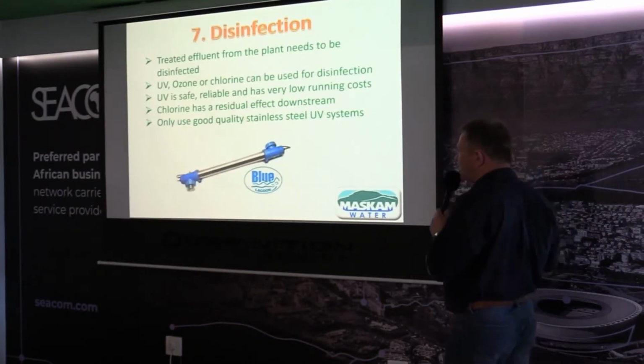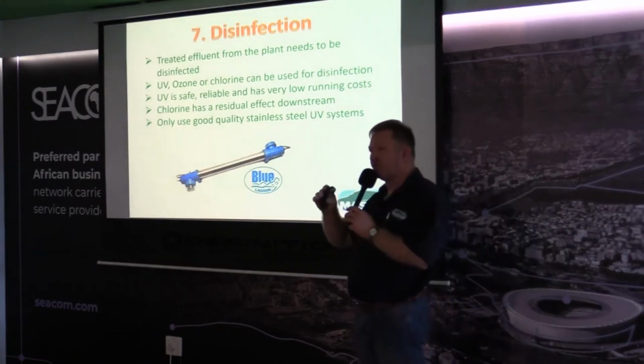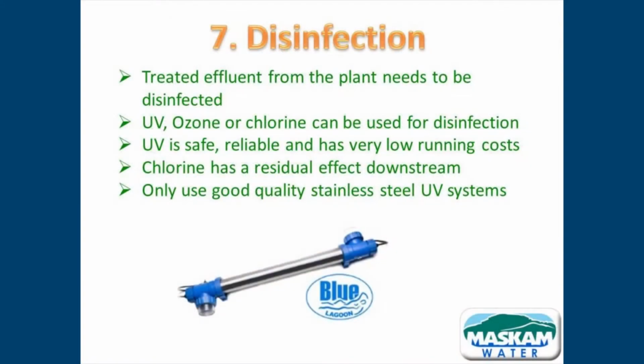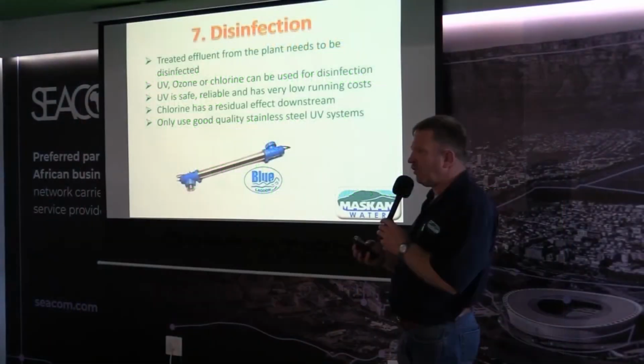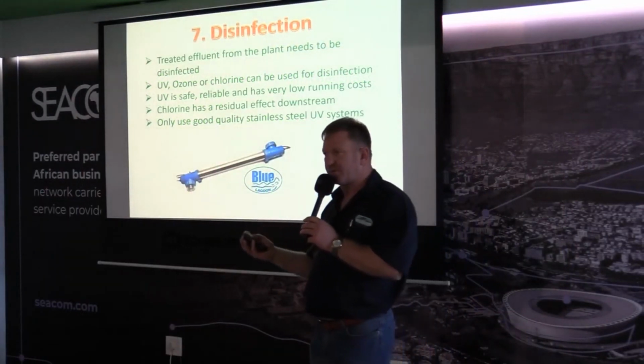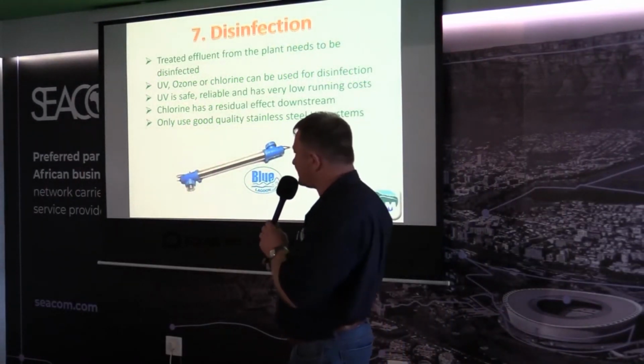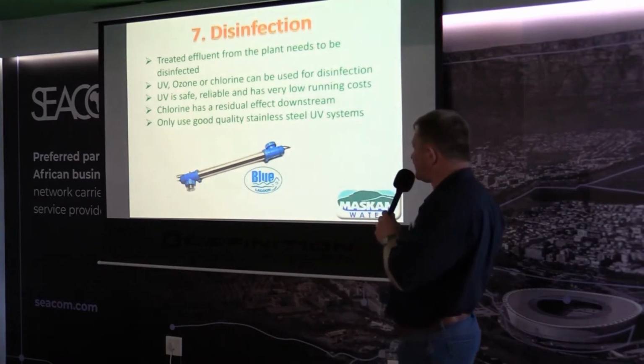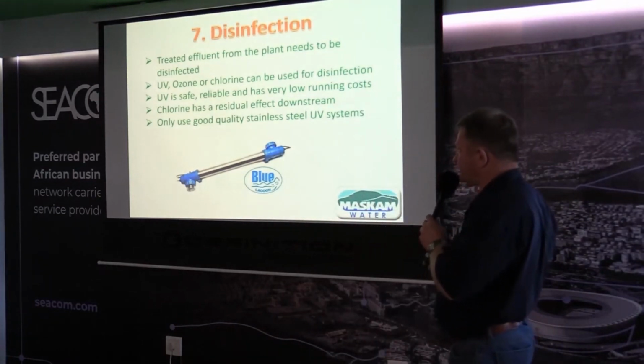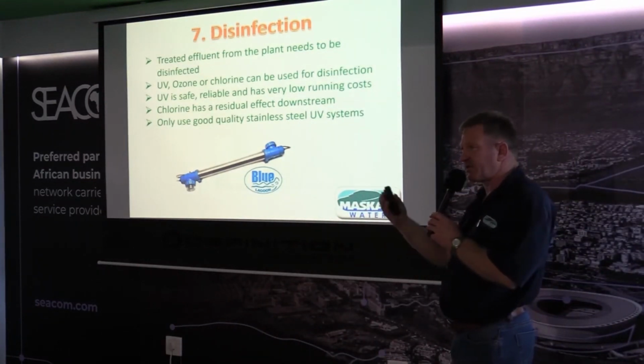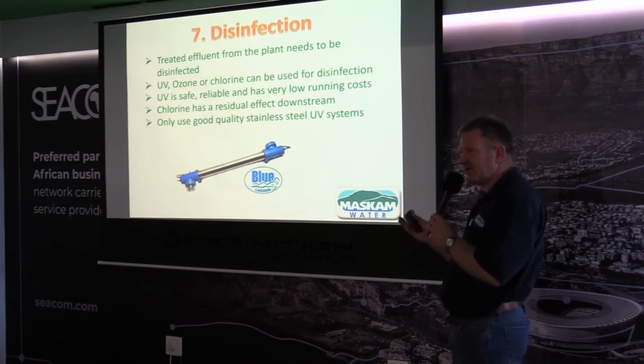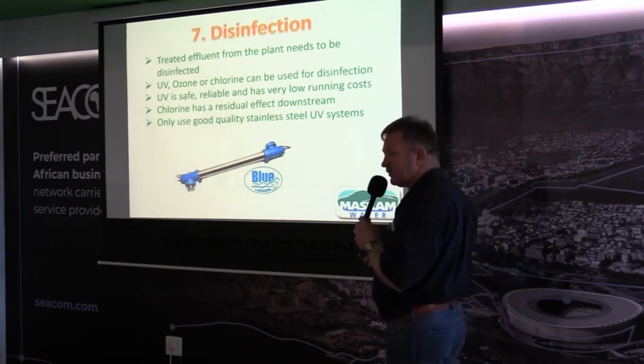And then lastly, we need to disinfect. We cannot disinfect the water in the system because we need the good bacteria to digest the wastewater. So once treatment is done, then we go for disinfection, which can be UV, chlorine, ozone, or on farms, sometimes peroxide is used as well. I prefer not to use that in the cities because not everybody knows how to handle peroxide, but it's possible to do that if you have an application where there's already peroxide on site and they have the safety measures in place for that.